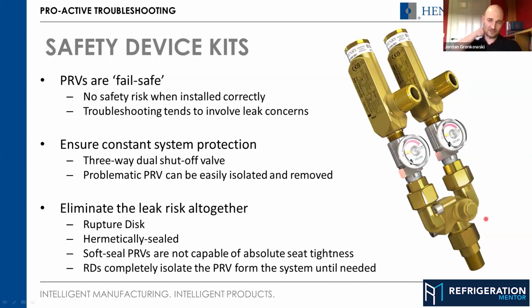The older models, some of our legacy three-way valves are longer valves with a piston that cycles back and forth to shut off one port or the other. And you really just have to look at the stem and see, is it in or is it out? To figure out. Back seat it or front seat it. Back seat or front seat, exactly.